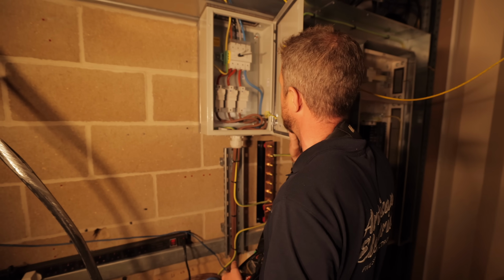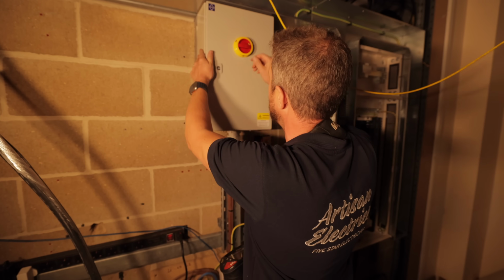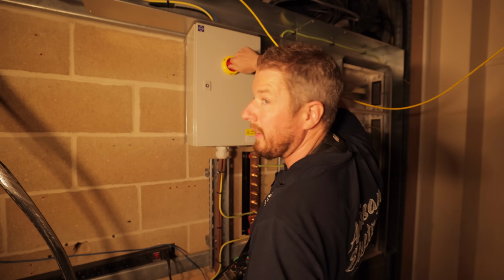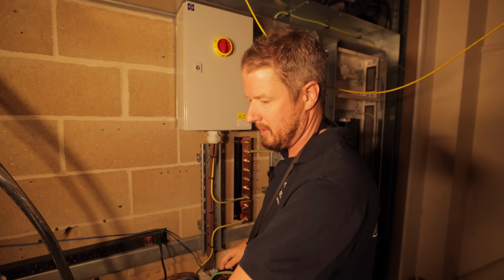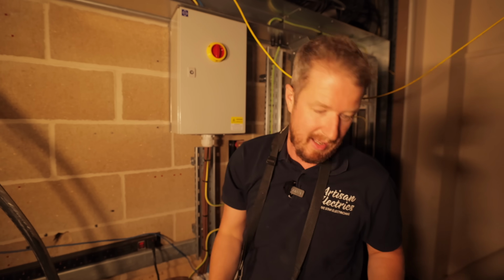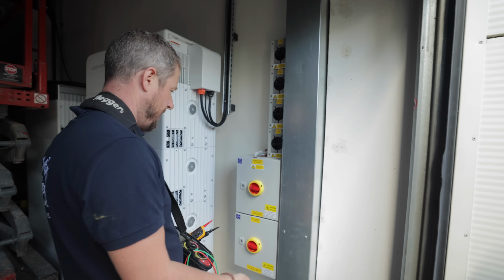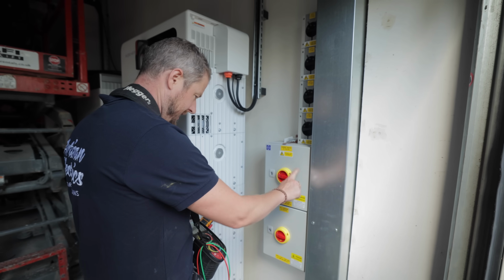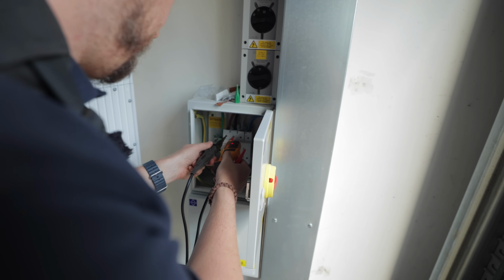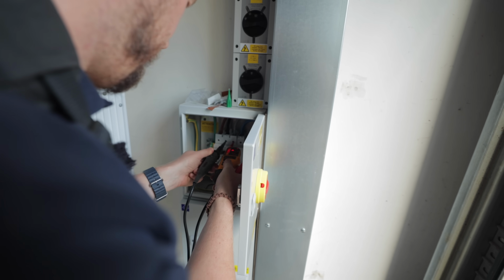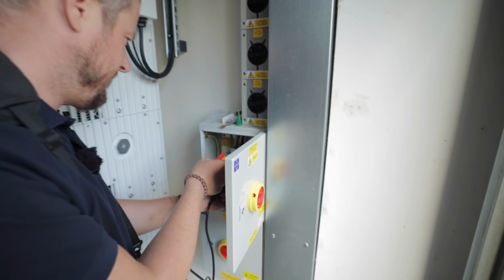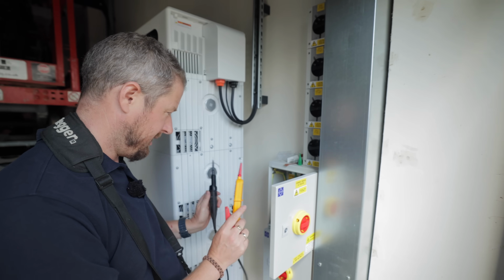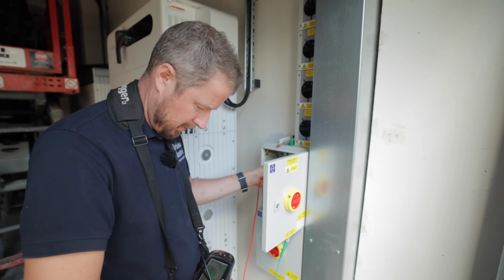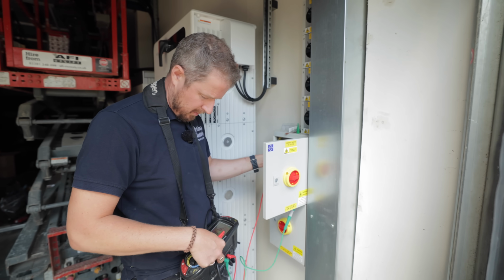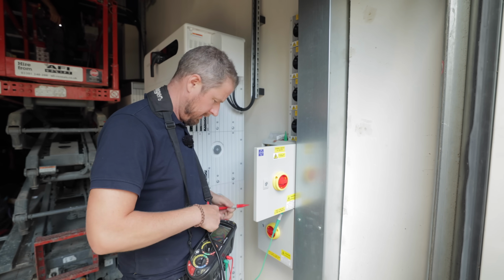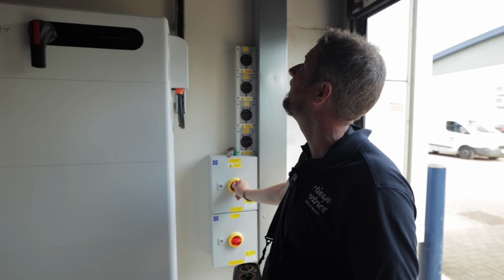Now we can close this up and switch this on here. That should take power over to there. Let's test it. So now the power comes in from here, and we test rotation, rotation right, rotation right. Our phase rotation is all good there. And then we do an earth loop impedance test here as well, 0.11.